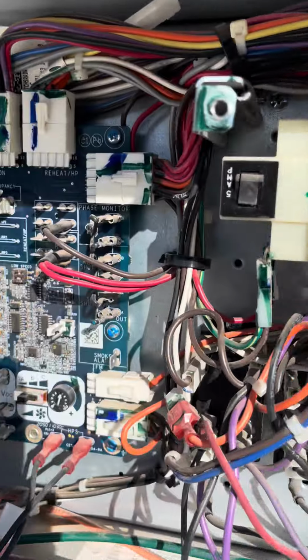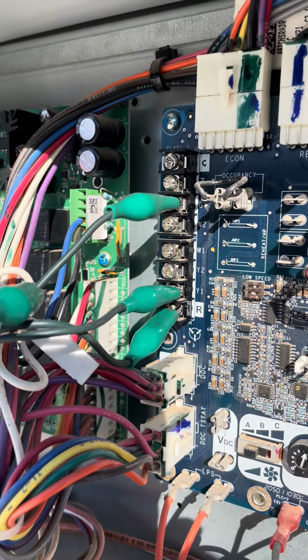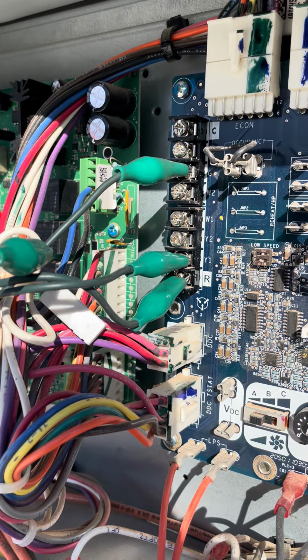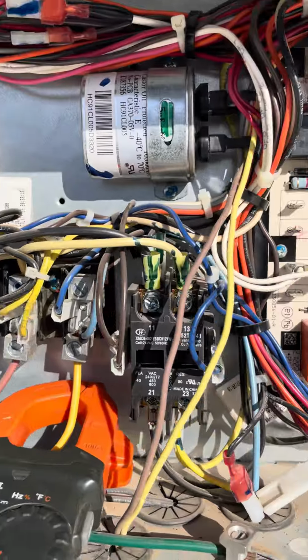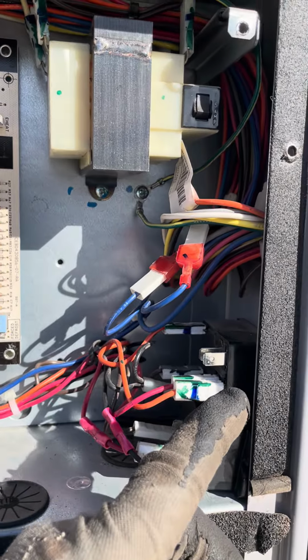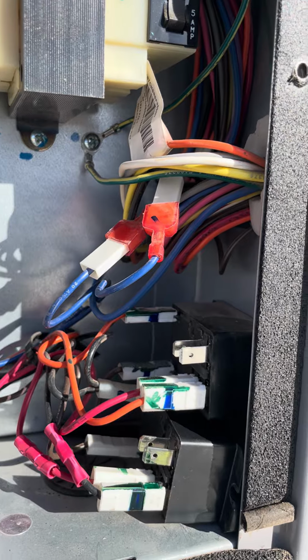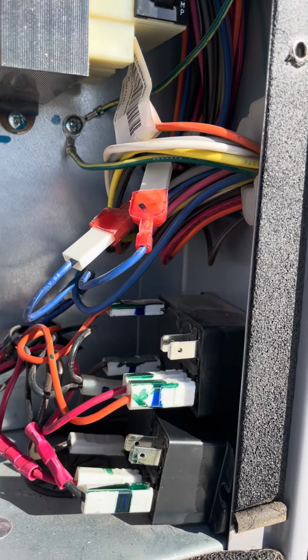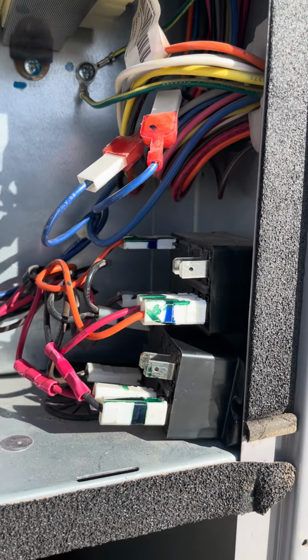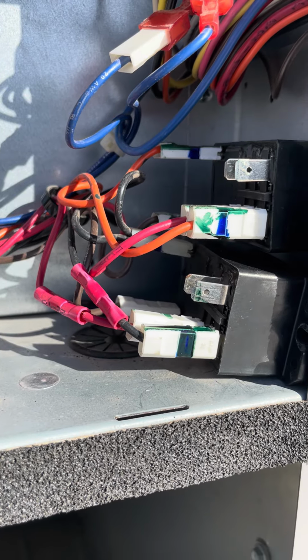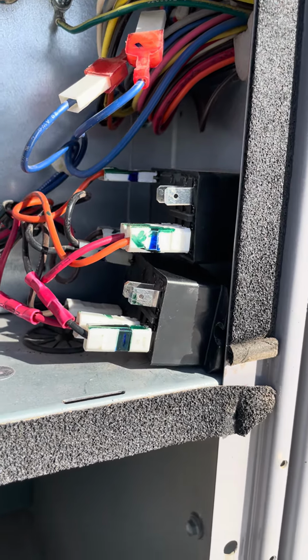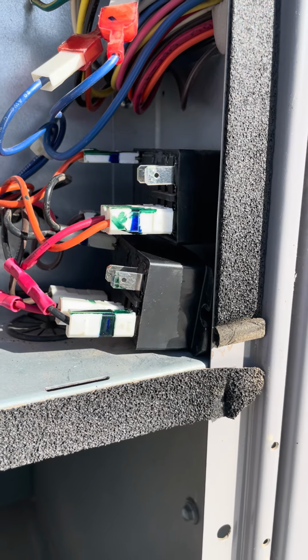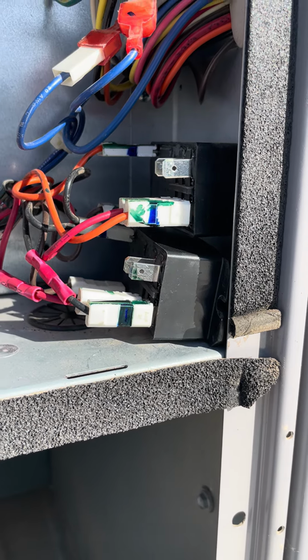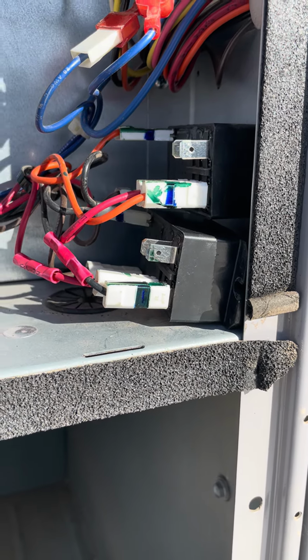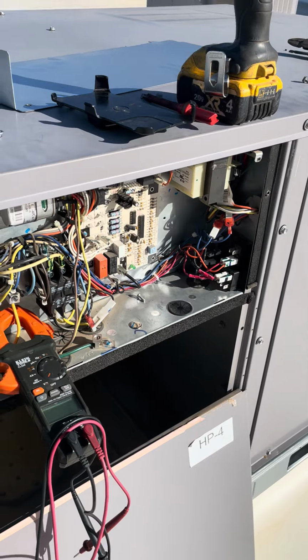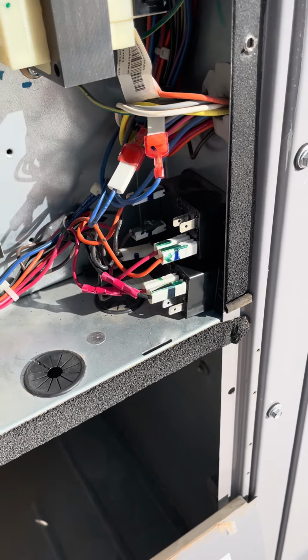And see, we're testing the unit for Y1 and G. So we're in the cooling mode right now and it's heating. The top relay is the one that's supposed to be heating. That one would energize in the heating mode. I'm going to show you what's going on with this relay. So I tested, and the bottom contacts is not allowing the voltage to go through. So same thing again.